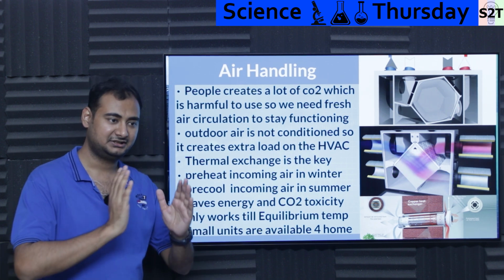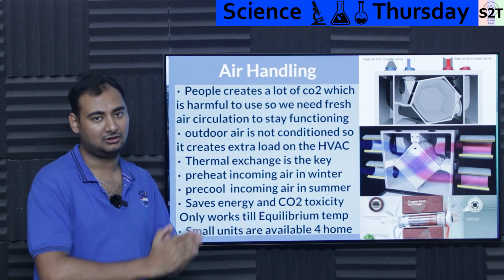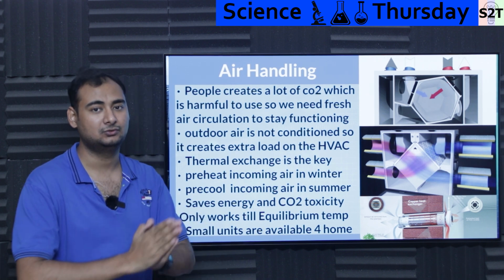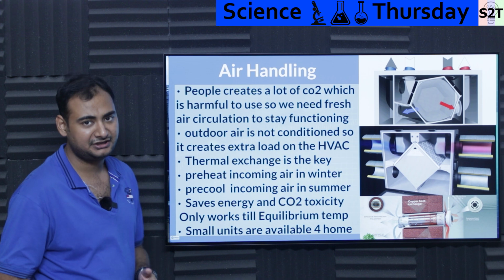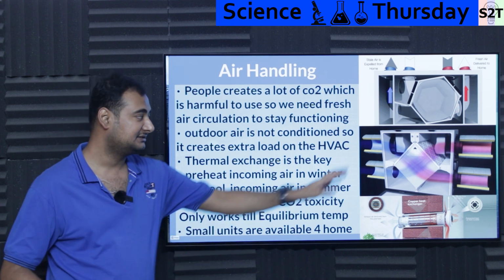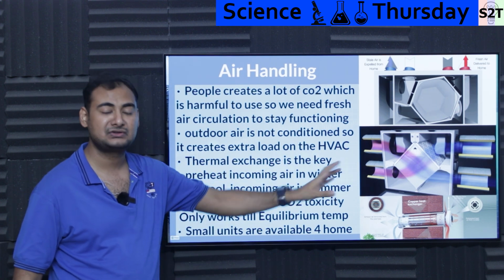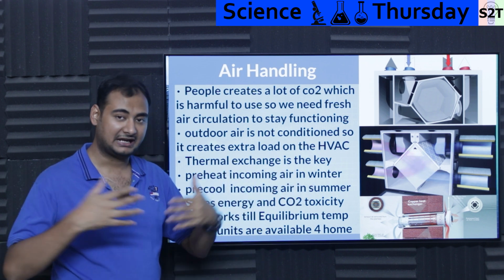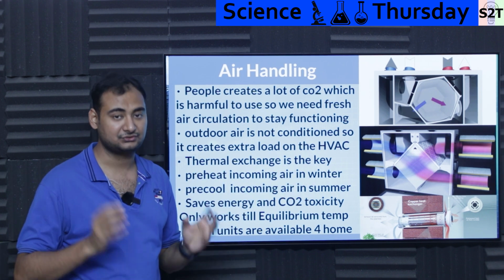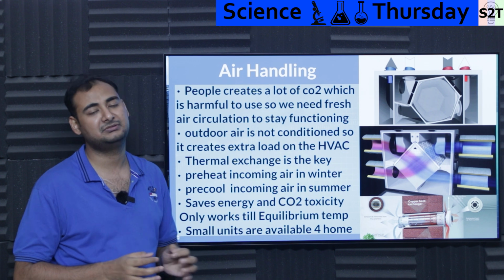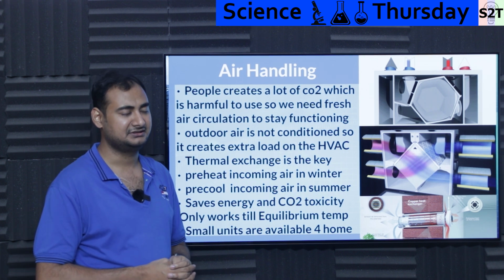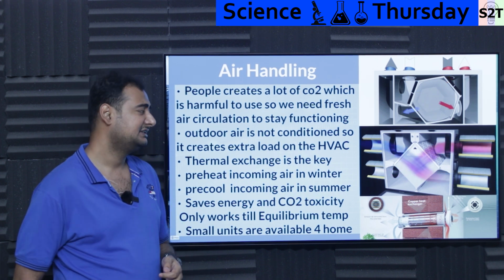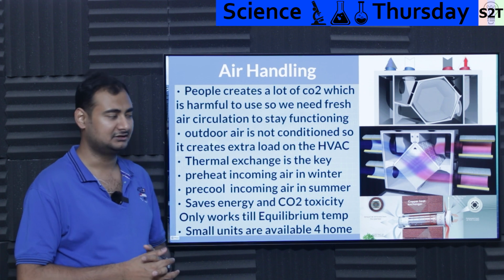So it's the same thing: either you pre-cool hot air or you preheat cold air, one in winter, one in summer. This is a completely passive device. The only consequence is that, since it's a heat exchanger, it does have flow restrictions, so your fans consume a little more power, but it's minor, especially with clean air filters.